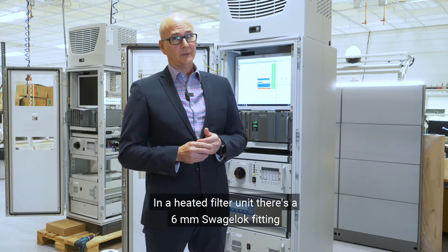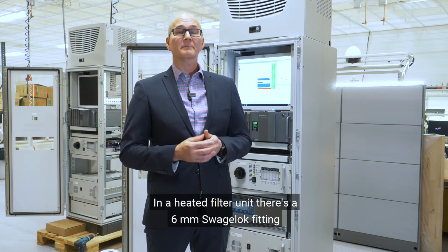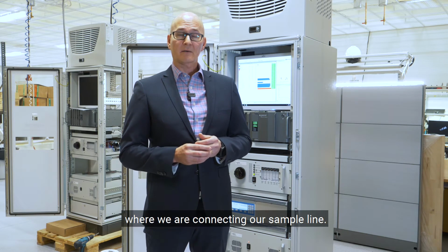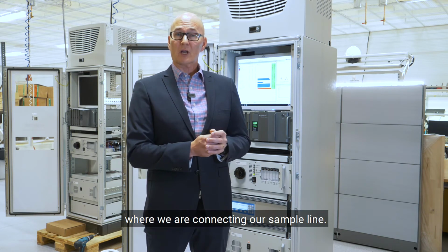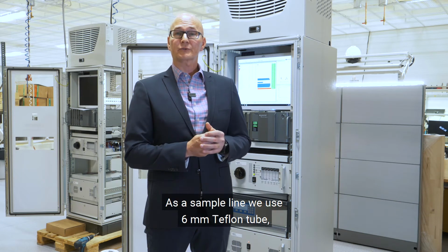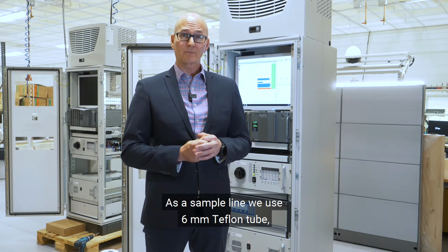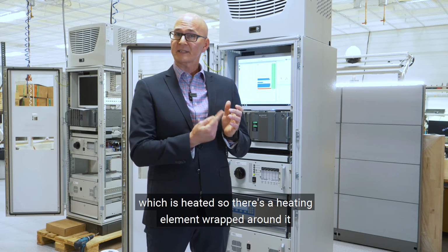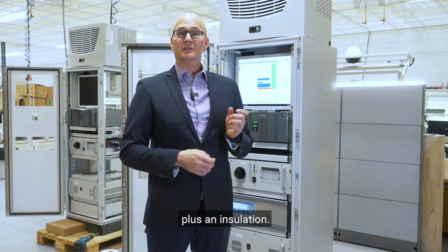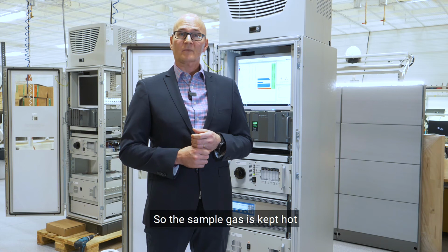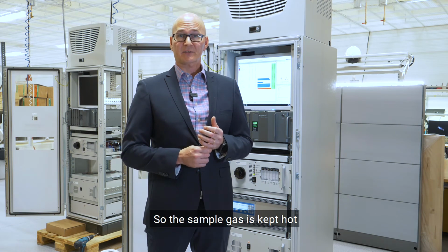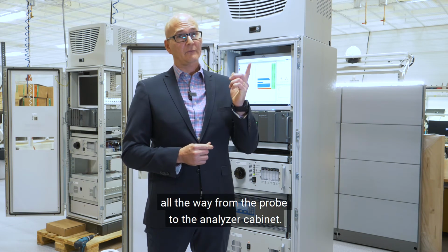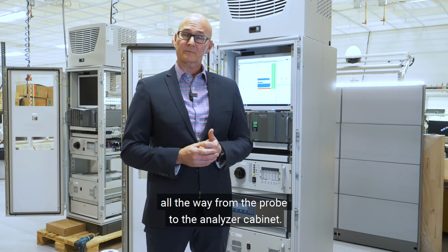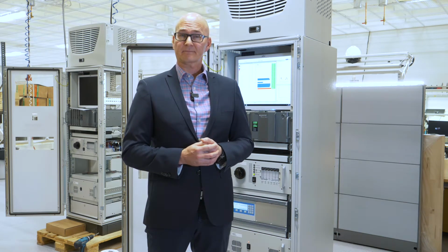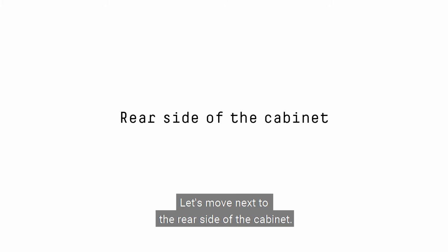In a heated filter unit, there's a 6 millimeter Swagelok fitting where we are connecting our sample line. As a sample line, we use 6 millimeter Teflon tube, which is heated. So there's a heating element wrapped around it, plus an insulation. So the sample gas is kept hot all the way from the probe to the analyzer cabinet. Let's move next to the rear side of the cabinet.